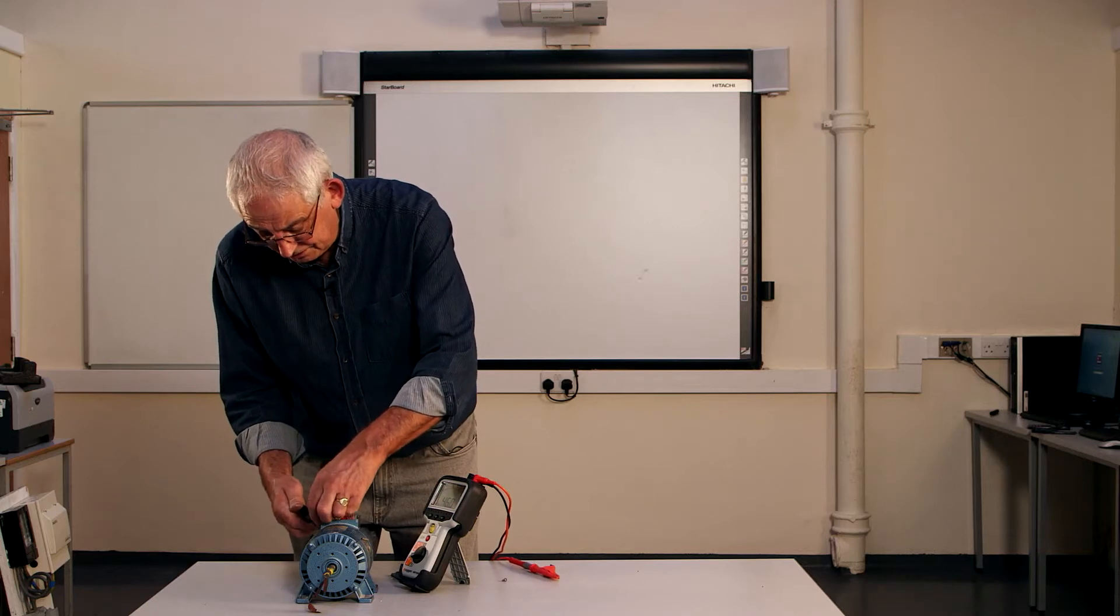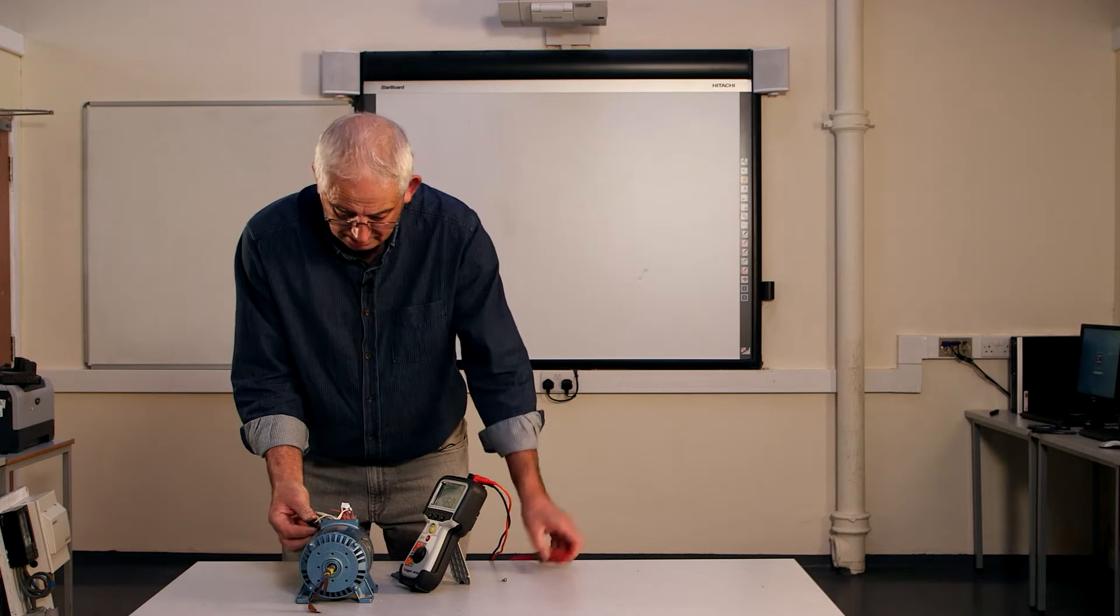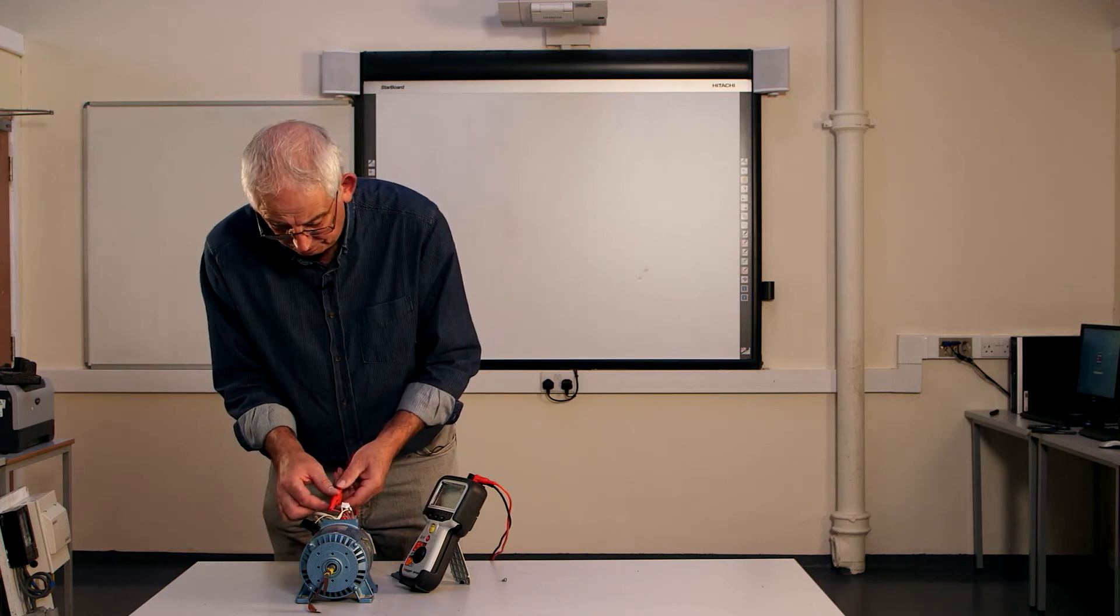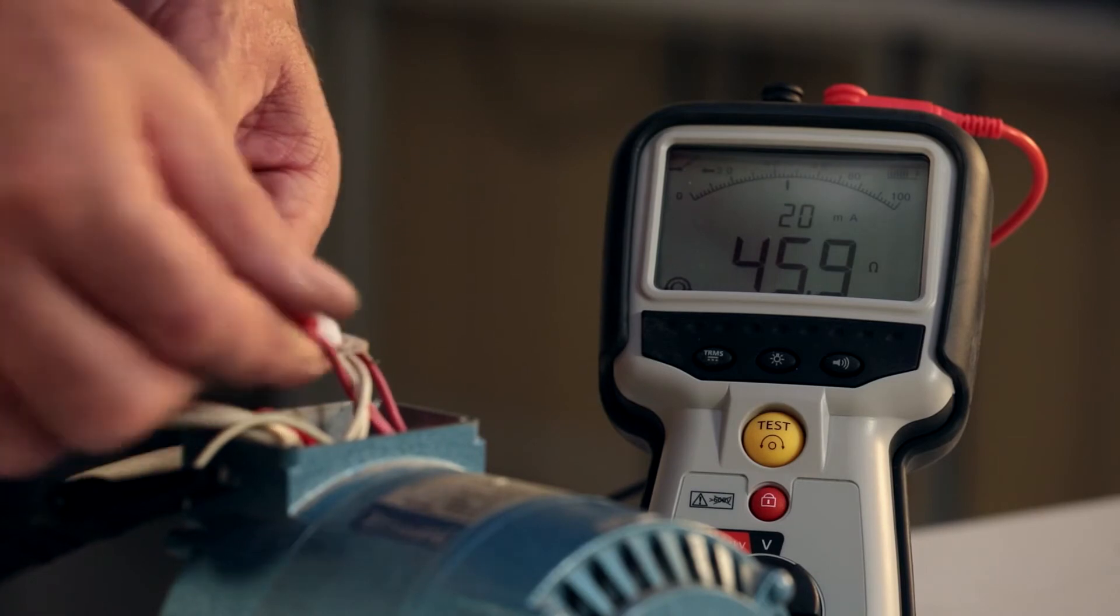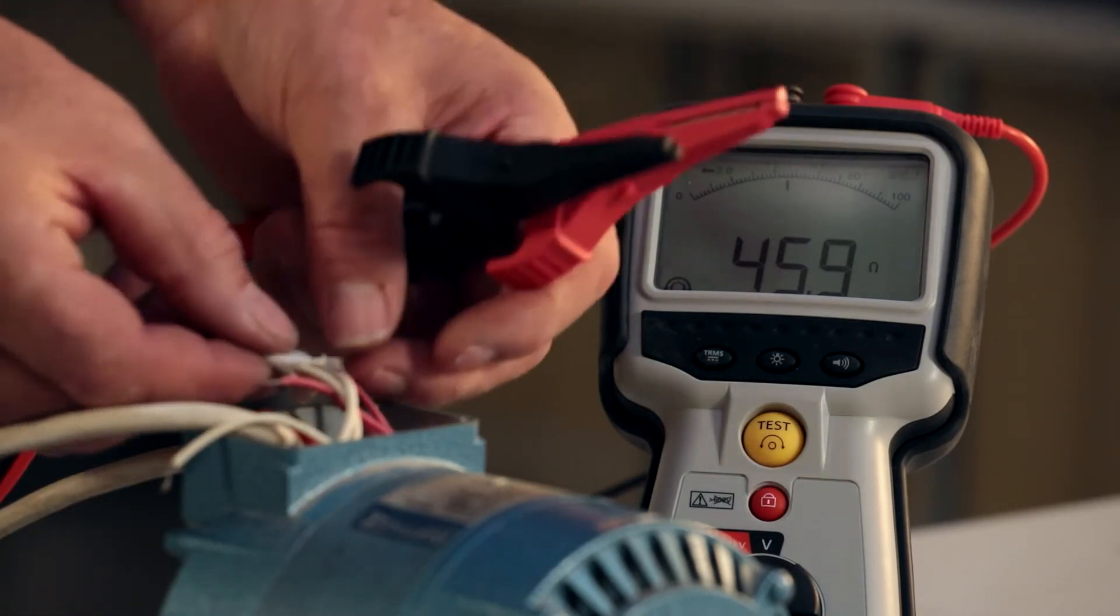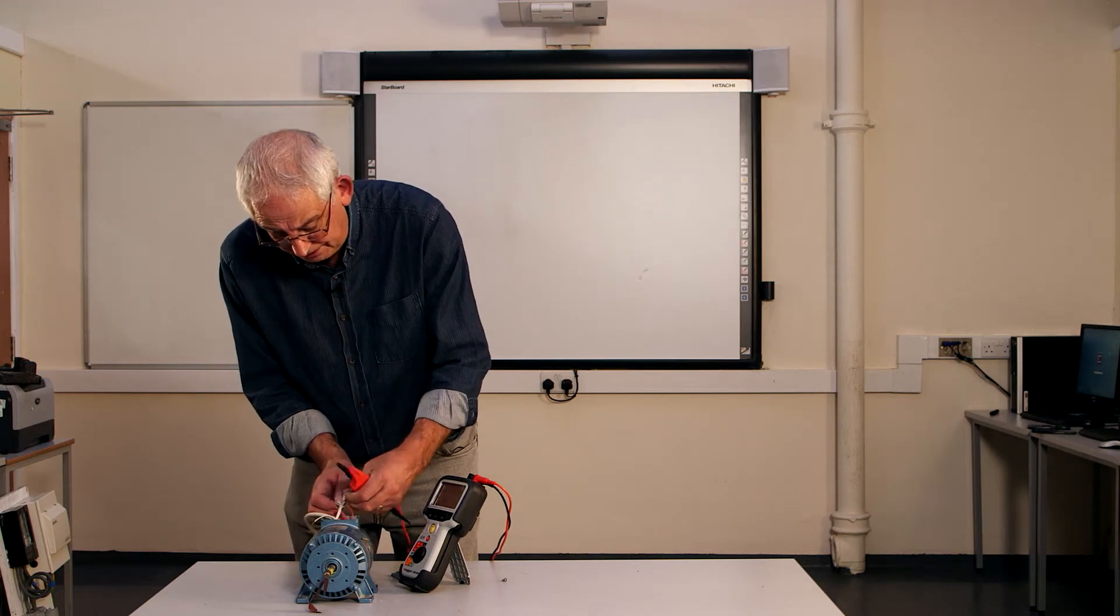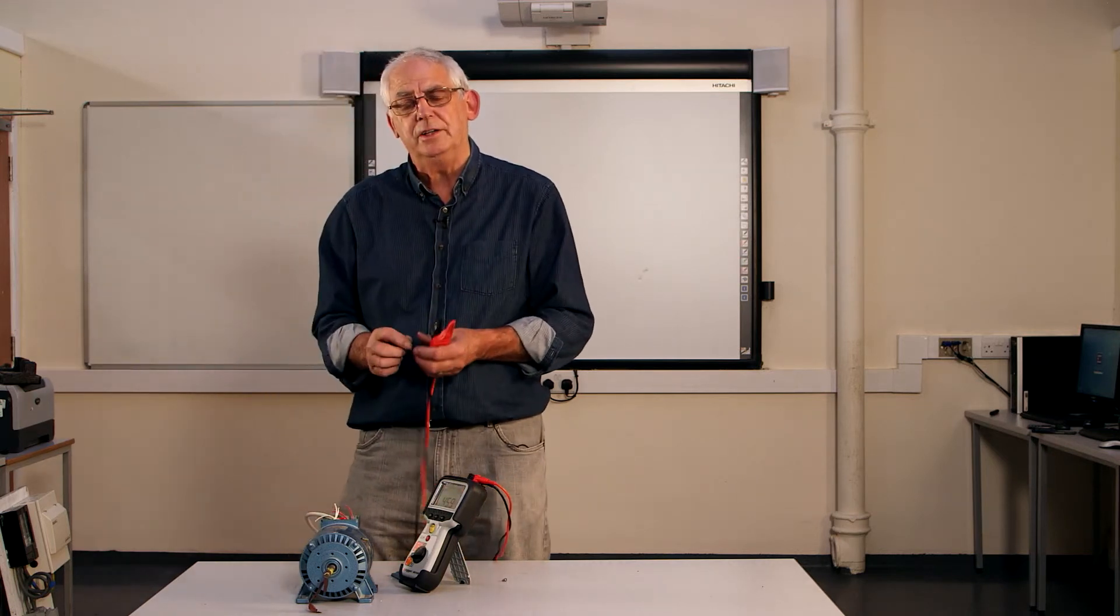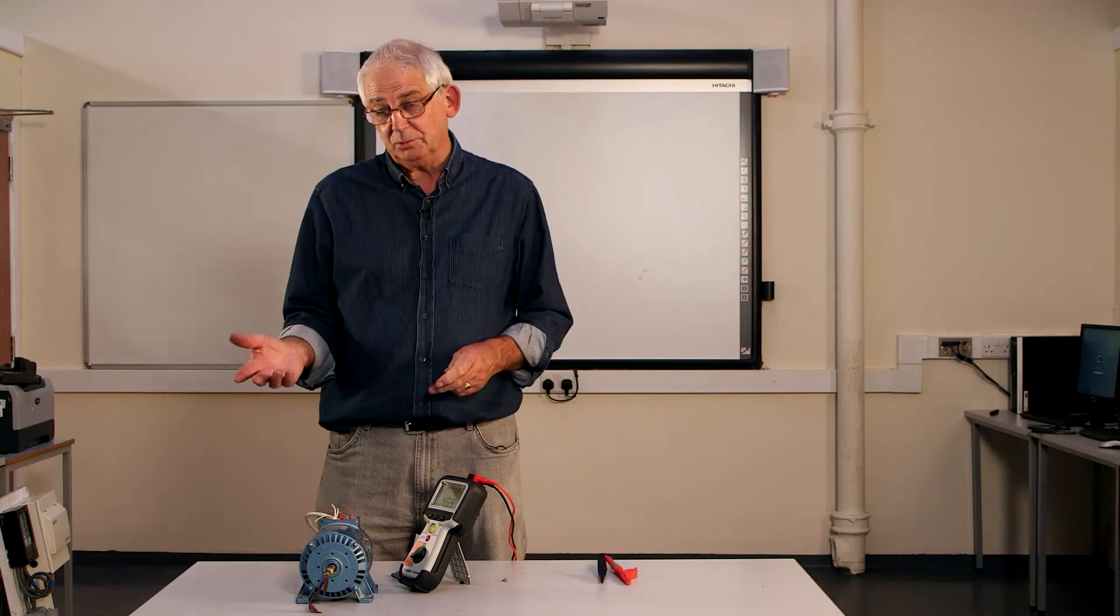Just check the last winding now to make sure that it's the same value. And again, 46. So at that point, I know that all of these windings are the same resistance value, so the motor is going to be very well balanced and it should work okay.